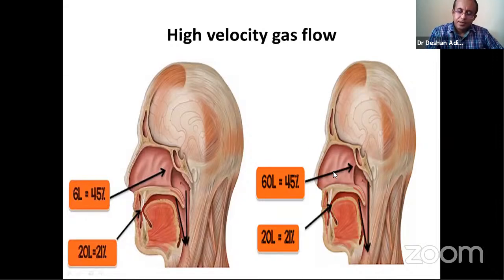And the other thing I wanted to explain is, because of this high gas velocity, there is washing out of your carbon dioxide. So assume that 60 liters per minute is flowing with 45% oxygen, and during exhalation, what usually happens is the exhaled air will fill up your nasopharynx and the nasal cavity and comes to the nose. Majority will go through the nose and a little amount will come to the mouth. But when you apply this high flow, you can see that this entire space is going to be filled with oxygen-rich gas. So the dead space is going to be filled with this oxygen-rich gas. So during the next inspiration, you will be taking oxygen-rich gas instead of carbon dioxide-rich gases.